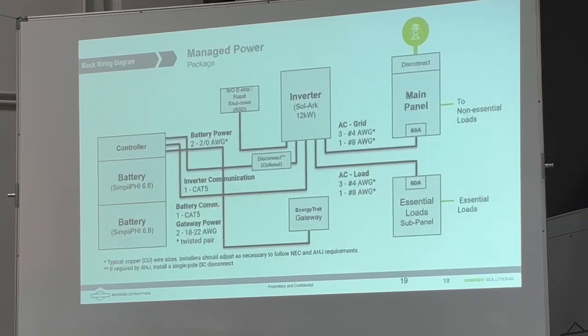Right, that big difference. So here's what a wiring diagram would look like for a managed home backup plan where you've got an essential loads panel that stays live in a grid down event, but the main panel goes down. And I'm mostly giving you this for the wiring diagram. Like I said, I'm going to give you all these slides so you can take this home. We've got recommended wire gauges based on the NEC code, etc. You can change those. You want to make sure you're always following code with them. Depending on cable runs, it might change a little bit.